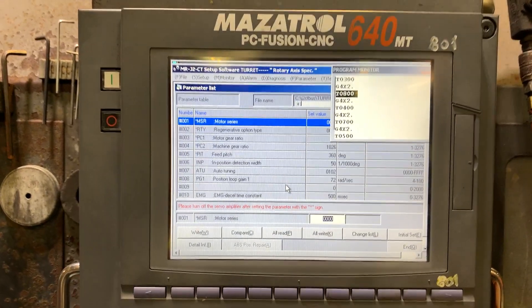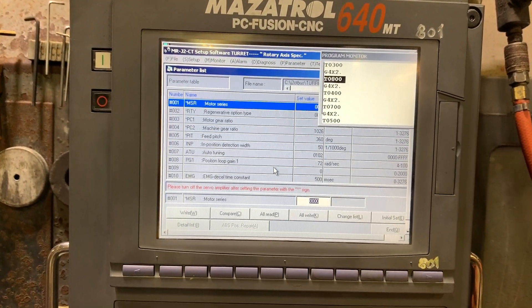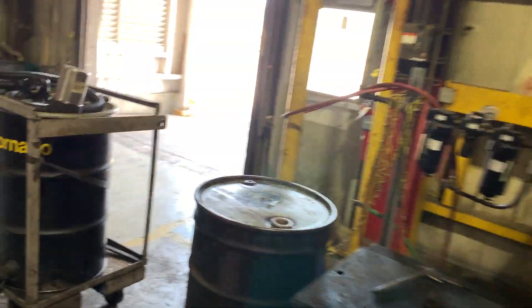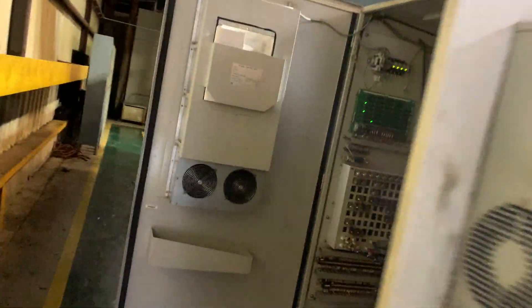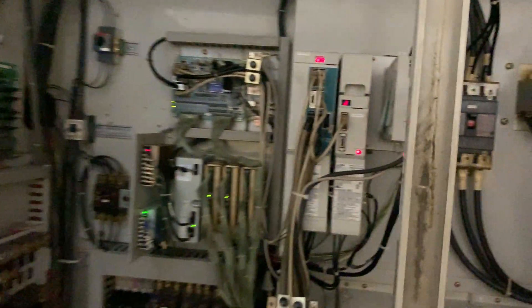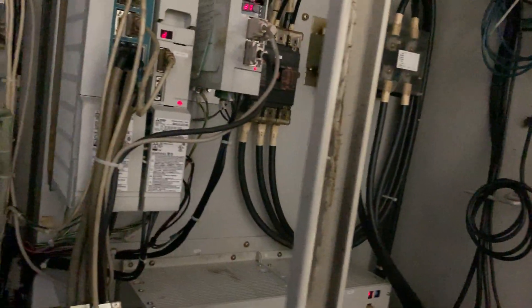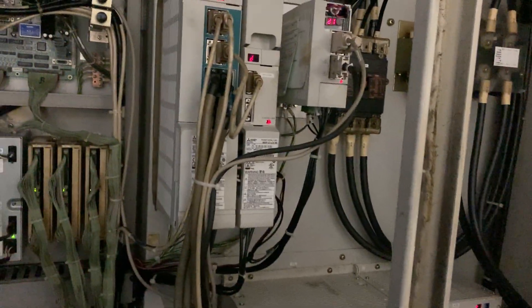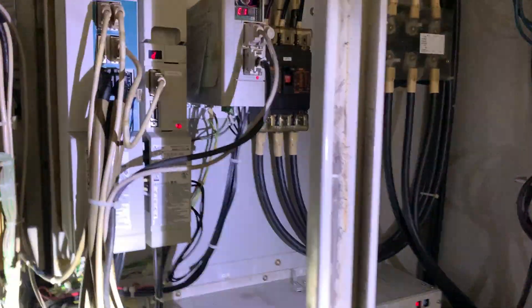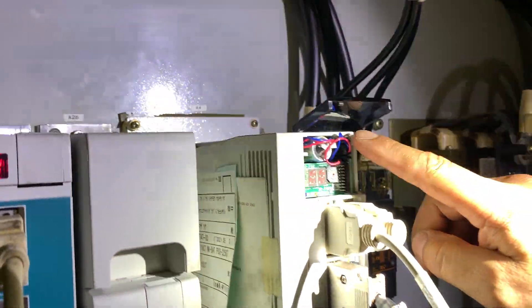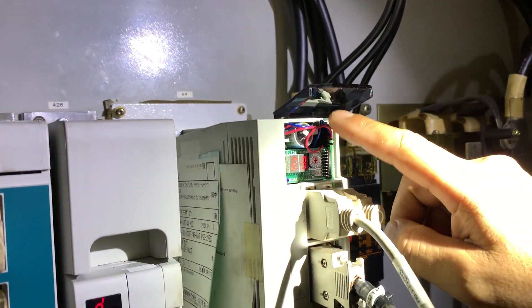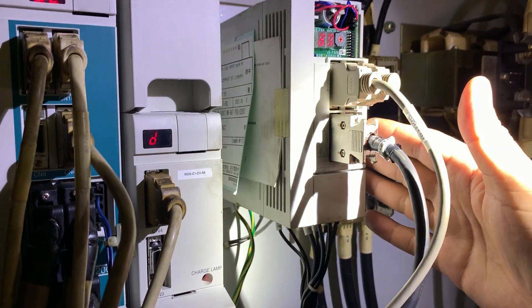Okay, the MRJ2 has a battery. Let me show you where it needs to be changed because maybe the problem was that the machine was down since Saturday and today is Tuesday. So we have a flashlight. Here we have the battery on the MRJ2 drive.